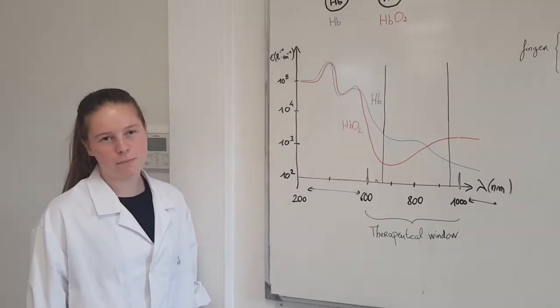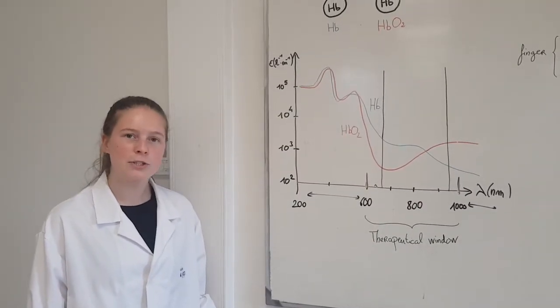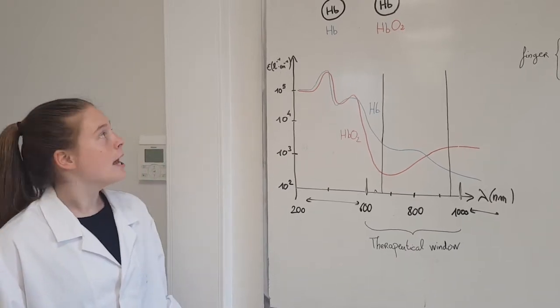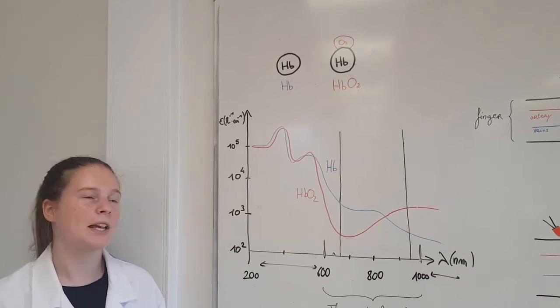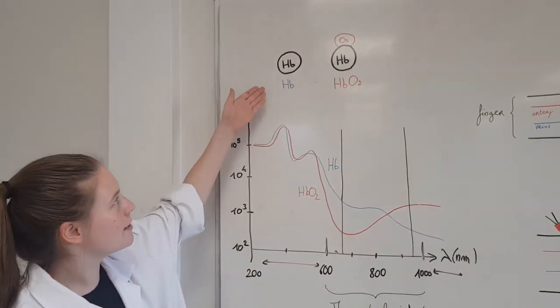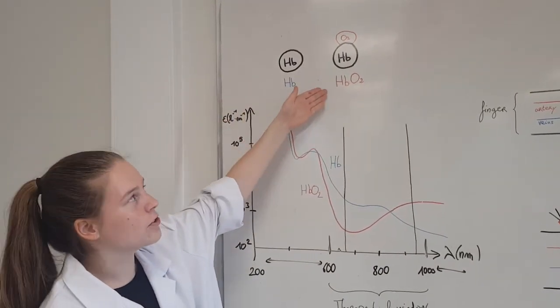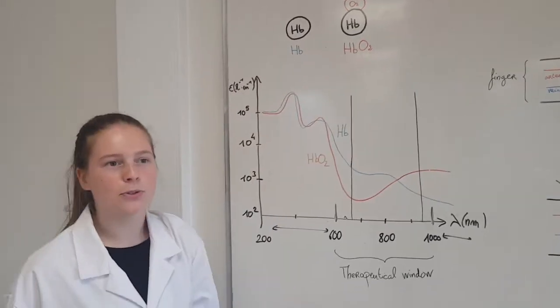To measure the oxygen rate of the patient, we must have a close look at two types of hemoglobins. Hemoglobins are molecules carrying oxygen in the patient's blood. We had a look at deoxygenated hemoglobin (Hb) and oxygenated hemoglobin (HbO2).